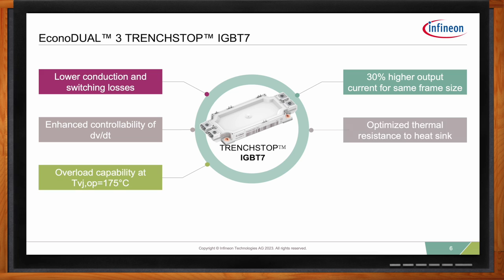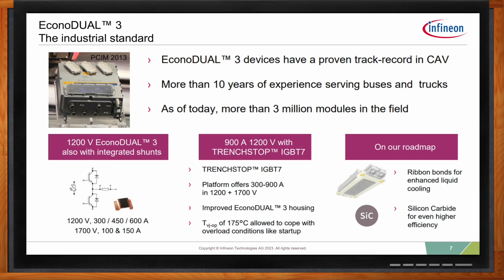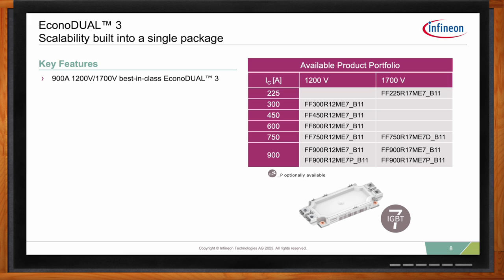Overload capability in the EconoDual 3 has been increased to 175 degrees Celsius. Besides e-bus, the EconoDual 3 package is used extensively in wind, solar, industrial drives, UPS, railway traction, and construction equipment. This is one of the most commonly used packages for drives and electric buses and trucks, with more than 10 years on the market and over three million devices running in the field. Regarding scalability, in the same EconoDual 3 package we offer both 1200-volt and 1700-volt versions, scalable from 225 amps all the way up to 900 amps, allowing customers to keep a common design and adjust to their power needs with minimal adjustment.